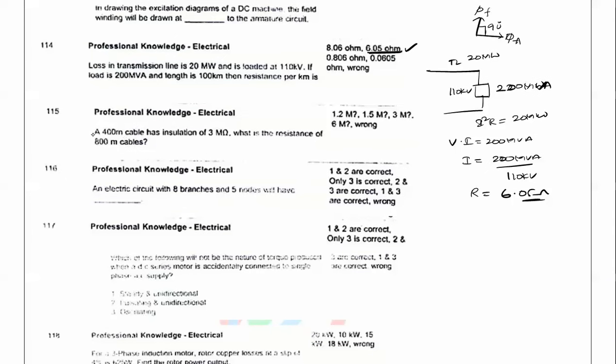The next question here is, a 400m cable has insulation of 3 mega ohms, and what is the insulation resistance for 800m cables? So the direct formula you can write is R2 by R1 is equal to L1 by L2. R1 here is 3 mega ohms. So 3 mega ohms into L1 by L2, that is 400 divided by 800. So 1.5 mega ohms is the answer.